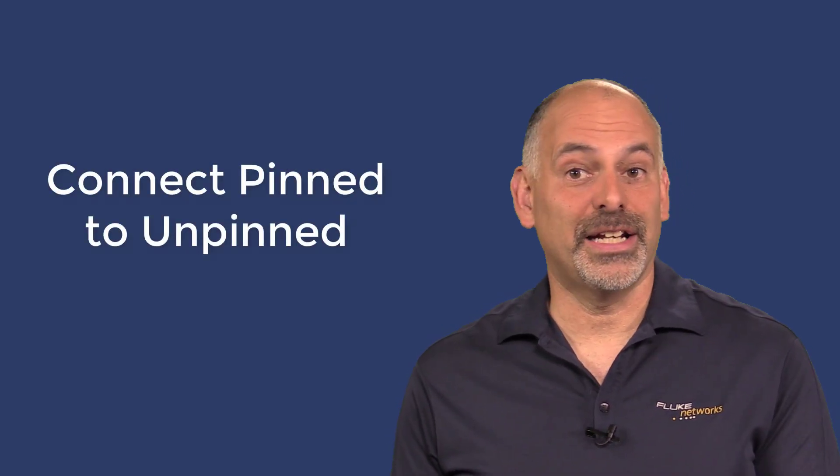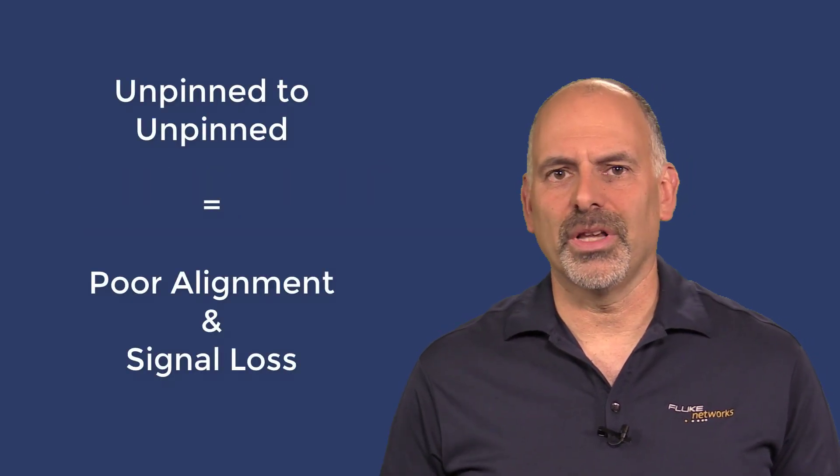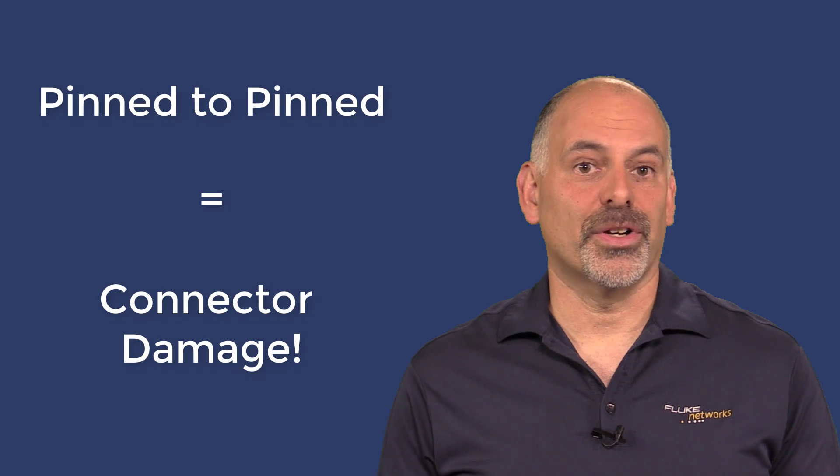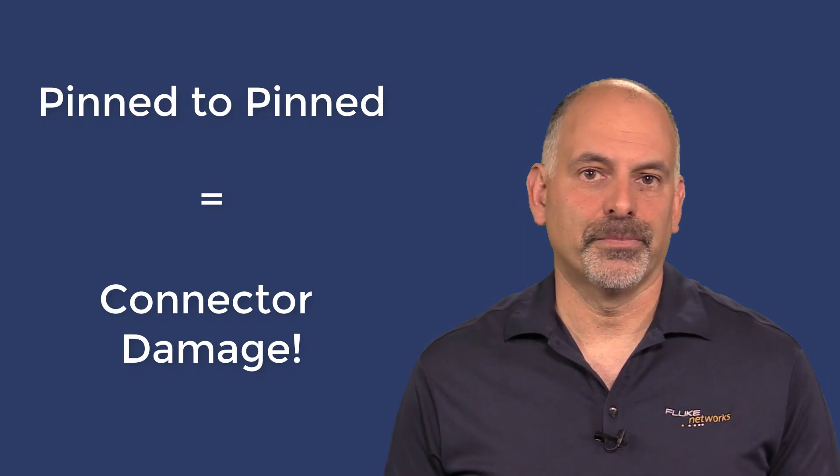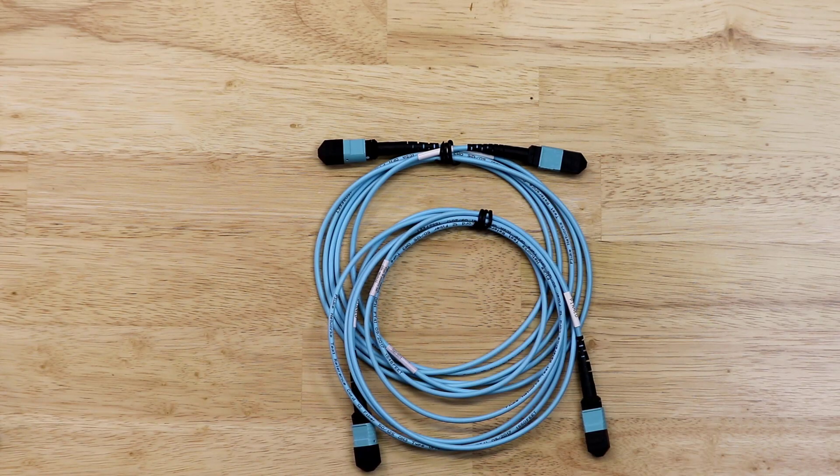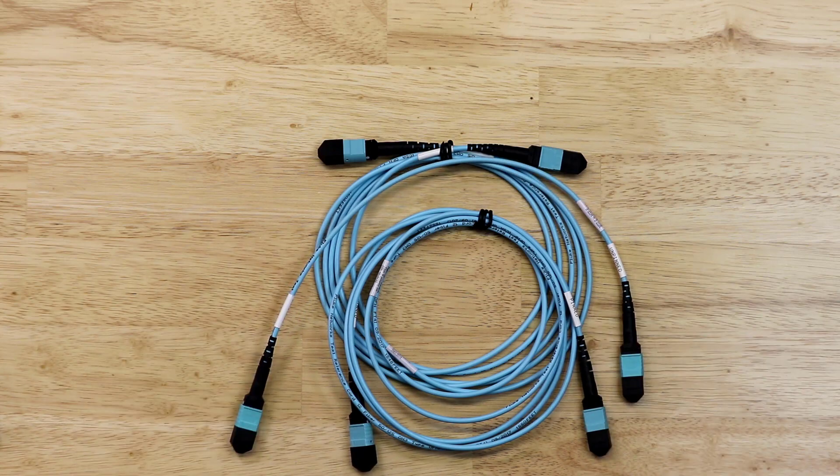Before we start testing the trunk cable, let's go through the cables I'll be using to test the pinned-to-pinned MPO trunk cable. This is a good time to talk about MPO connectors. It is important that we always connect pinned connectors to unpinned connectors. Connecting two unpinned connectors together will result in poor alignment and significant signal loss. Connecting two pinned connectors together may result in damage to one or both of the connectors. The first cable is a pinned-to-pinned test cable. The next cable is a pinned-to-unpinned test cable. Since we are using a pin-to-pin trunk cable, we'll also be using a short, unpinned-to-unpinned test cable as well.